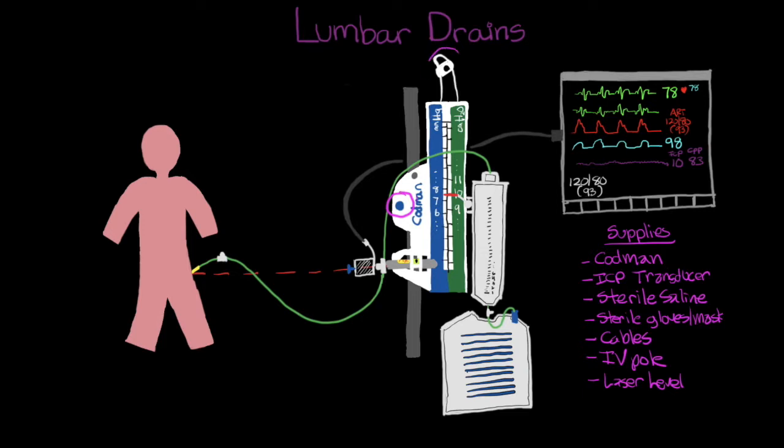There's also a string that's up here hanging off the top of it. This is important. You want to secure this to one of the hooks or somewhere on the IV pole, and this really just serves as a backup securement spot just in the event that that twist clamp were to fail. But our primary means for securing this is going to be that twist clamp right here.